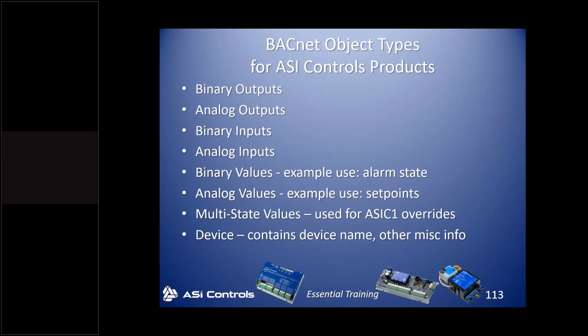For software points, there are binary values and analog values — binary is on/off, analog is numeric. A binary value could be an alarm status point; an analog value could be a set point not related to a hardware input or output but something you might want to see in the BACnet front end. We also support an object called a multi-state value — like an enumerated list where number 1 might represent one thing and number 2 something different. We use those for ASIC/1 overrides; we don't use multi-state values in ASIC/3s.